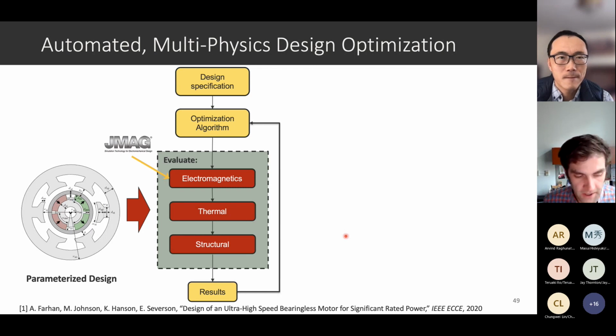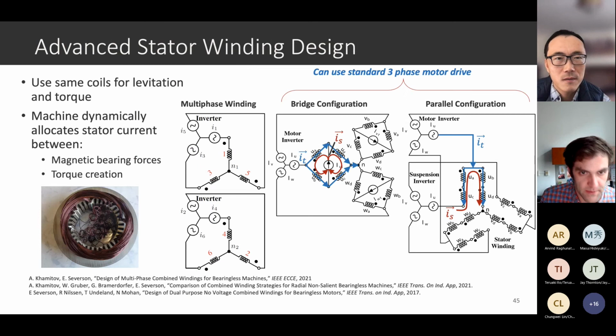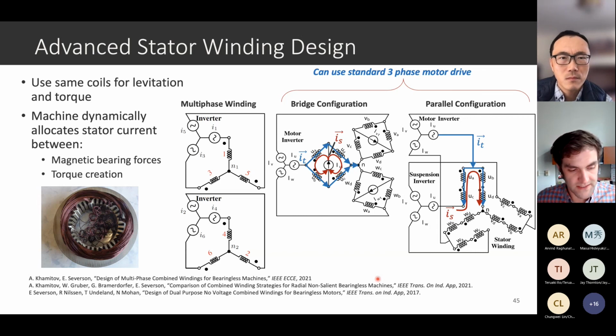Yes, you can. I think the classic example is trying to get rid of vibrations from the system. One reason I like this concept is that if you have an intermittent issue, where forces on the bearings occur at some operating points but not others, these advanced windings that use the same coils for levitation forces and torque give you a lot more degrees of freedom. You can have your regular motor performance and torque capability when you don't need levitation force capability, but then in those instants, like passing a critical speed or a compressor surge event loading your bearings, your motor drive can ramp up and generate forces that help your bearings out.